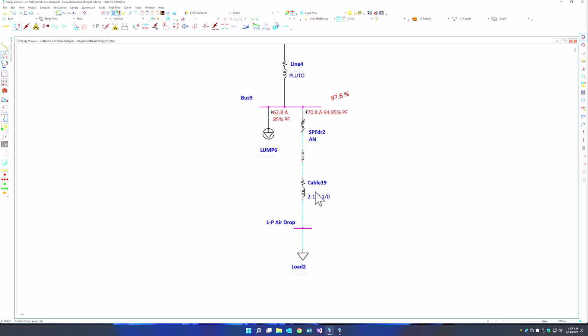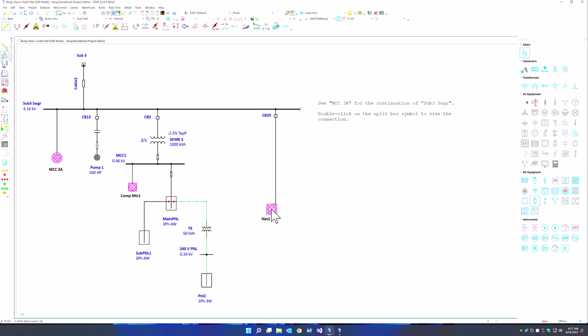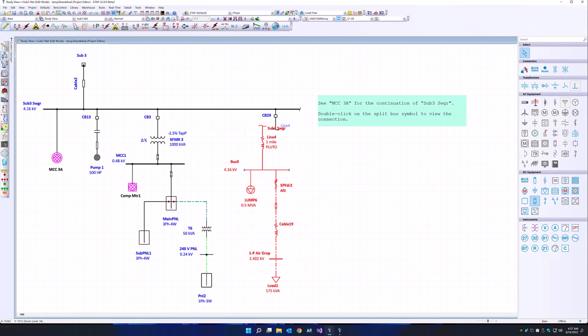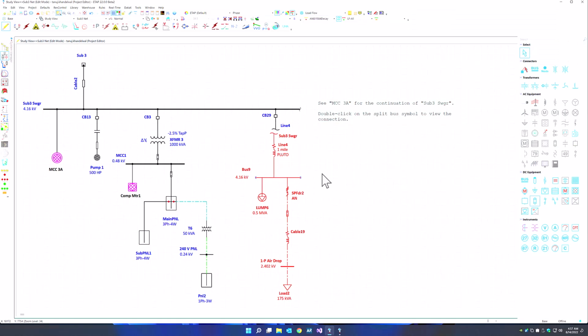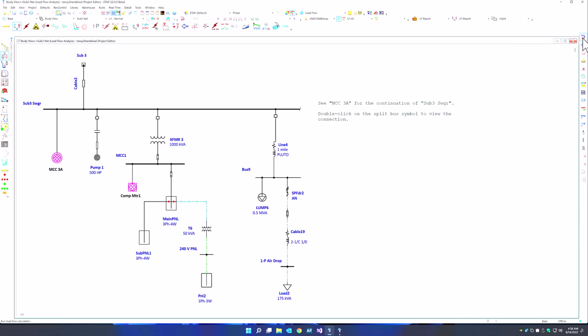When you go inside this composite network number 2, you can see this is the portion of the diagram that we put inside our composite network. To bring this diagram back, you can simply right click and expand or unhide this diagram. The diagram comes back grouped with remote connectors, which you can simply select and delete. Once that is done, you can run our load flow again, and you can see the flow remains exactly the same. It's 85.9. So using a single right click, you can convert any portion of the diagram into a composite network with single or multiple pins and bring the diagram back into its original condition.